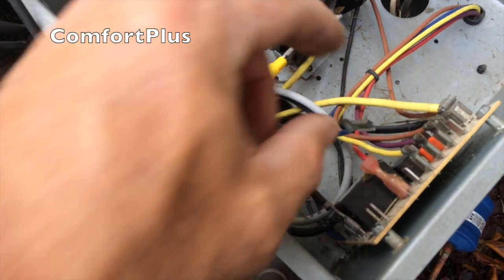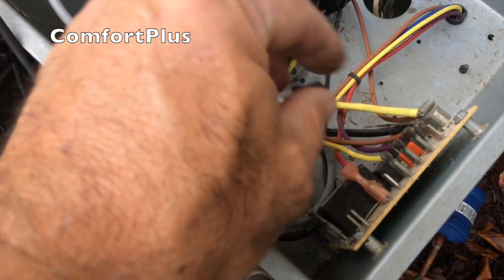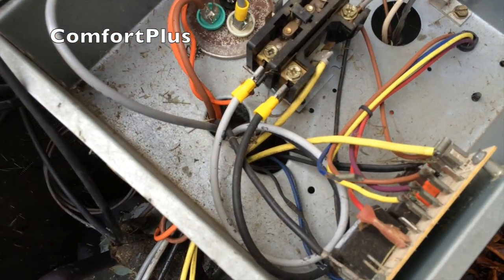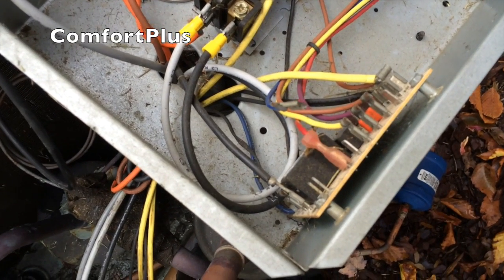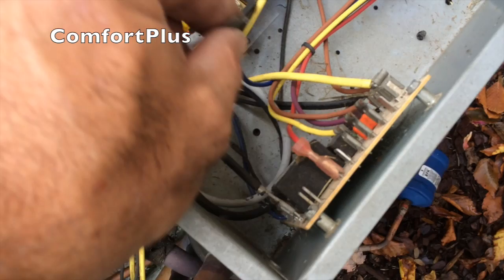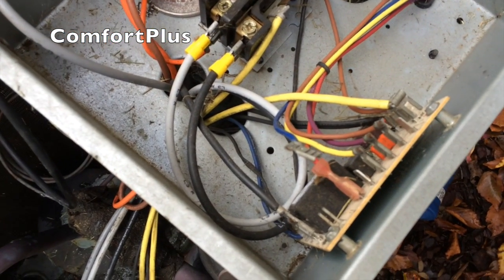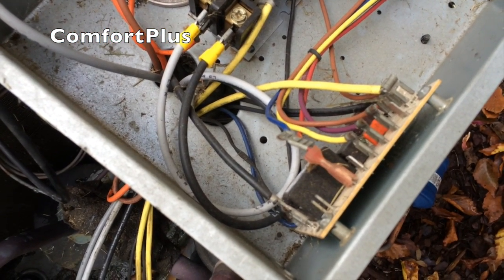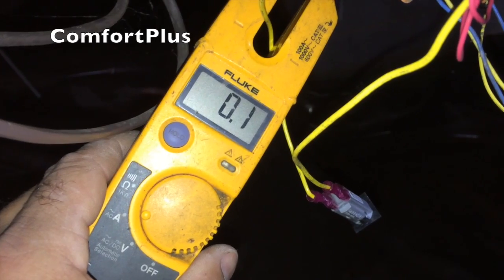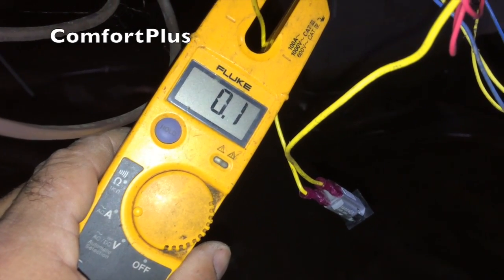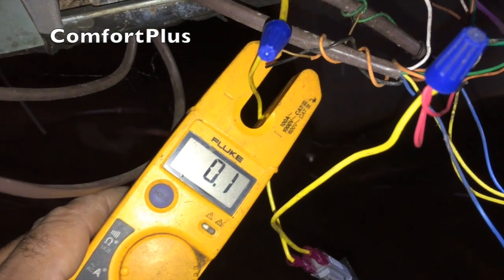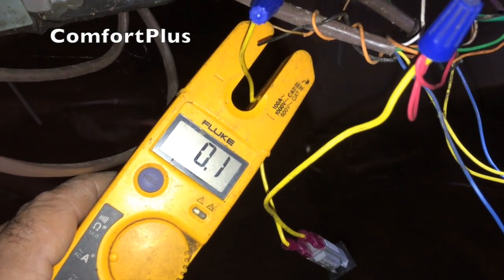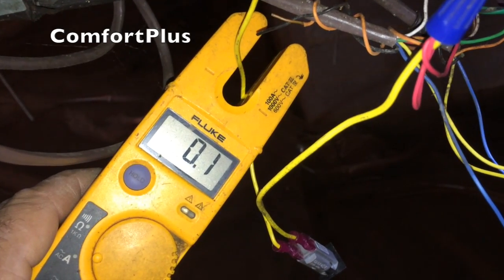Okay, I'm just going to pull the blue wire off out here. I checked it to common after I unplugged it, and it is not shorted, so I'm thinking we may have a problem out here, but I'm going to go back inside and hook it back up and make sure unplugging the blue does away with our high amp draw. And with everything reconnected in here, we're back to a 0.1 amp draw. So I'm going to go outside and investigate the defrost board and see what we can find wrong with it.